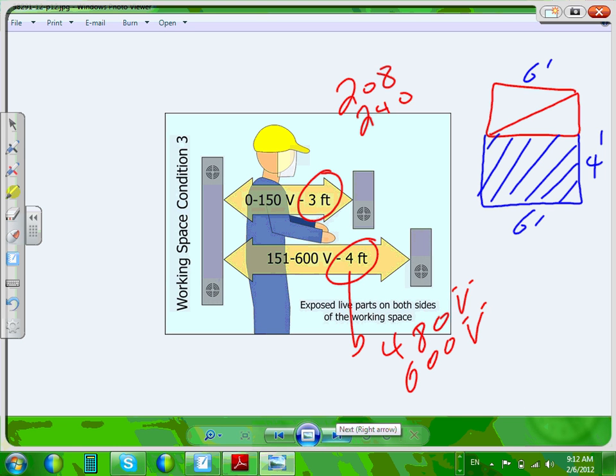Any question about this? Can I have thumbs up, guys, to make sure? Now the panels that you guys have with me, 208 and 120, you're going to make sure this is mainly for panels and anything that has an overcurrent protection device. Disconnects that have an overcurrent protection device too, that need maintenance, and fuses and so forth, it applies to them.